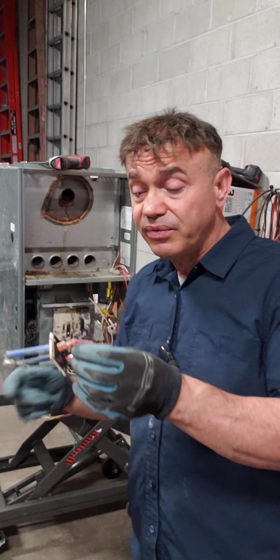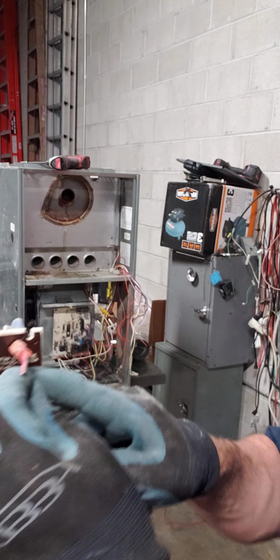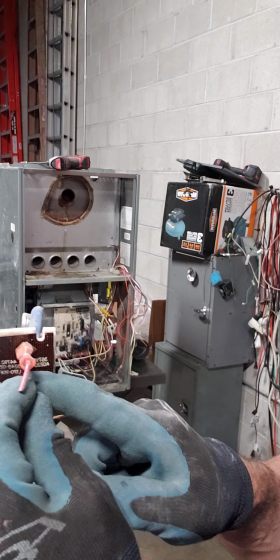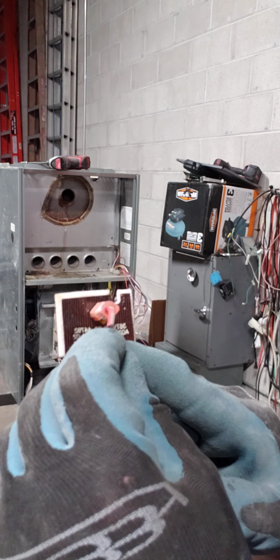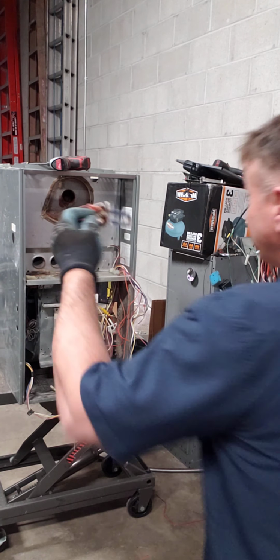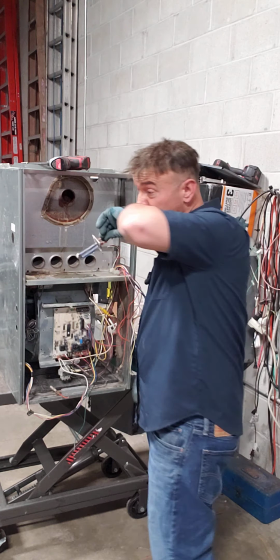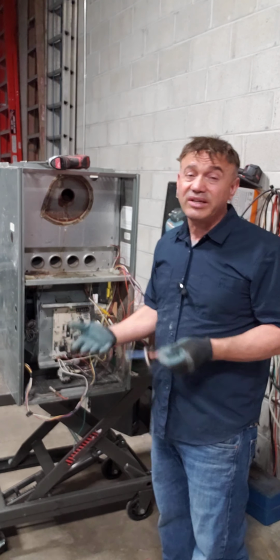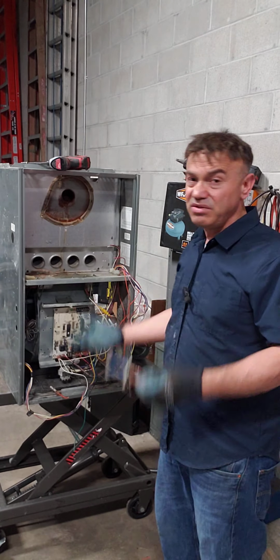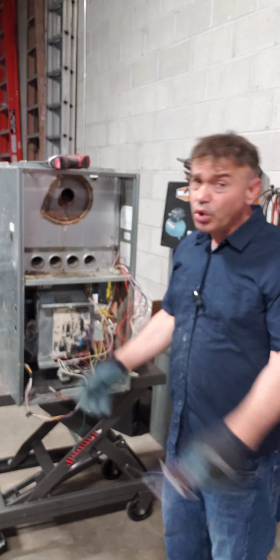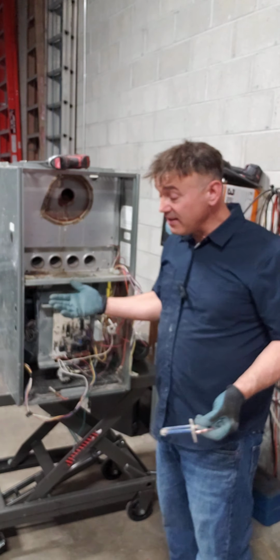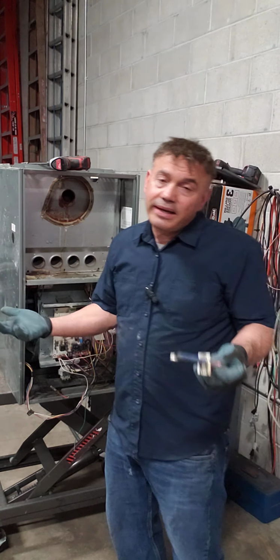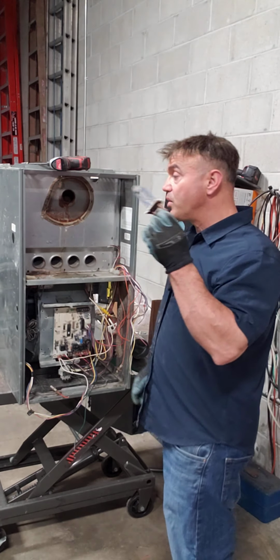Now it will cool down the furnace, as we said, 170, which is the cut-off, minus 20, you're going to get the cut-in, right? So 150. It cools down to 150, it's gonna come on, and it's gonna happen like that till they call me or they call someone. We go there and say, hey, change the filter, hey, don't close all the registers. Sometimes, believe it or not, some people have a return on the floor and they put a carpet on it by accident. Again, they don't know what they're doing. So you got the idea.